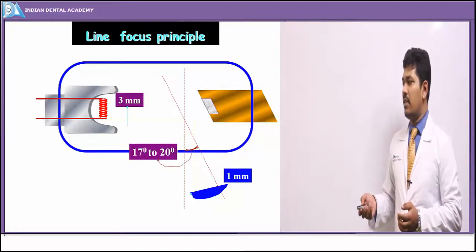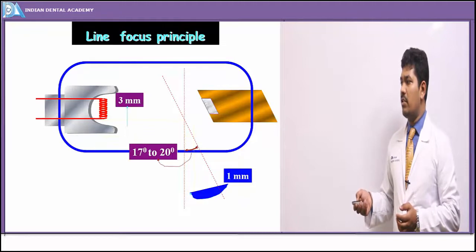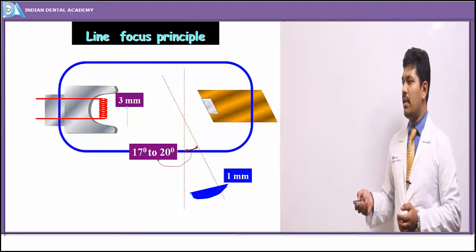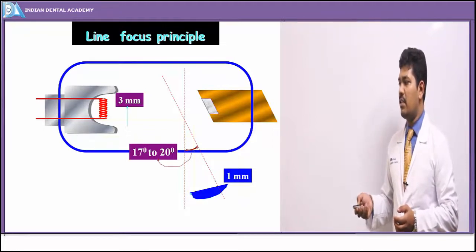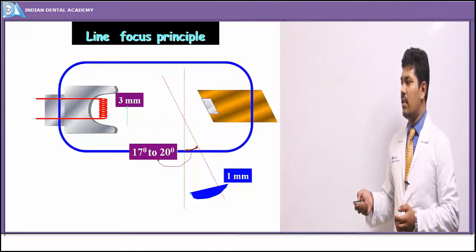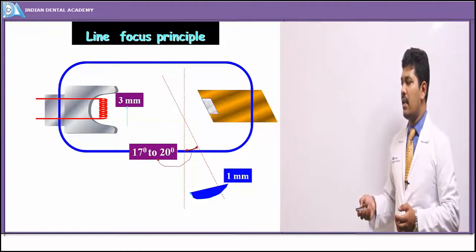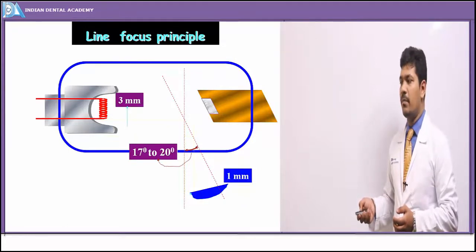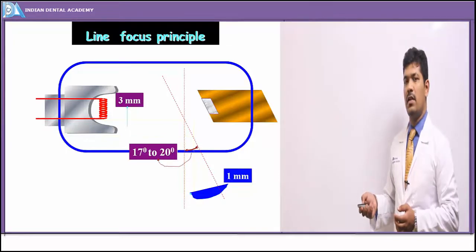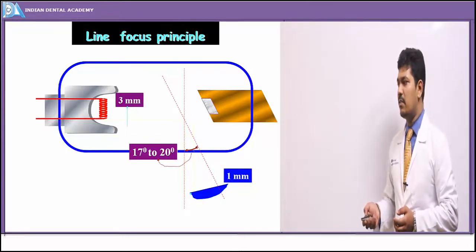As shown in the diagram, the actual focal spot is around 3 mm in dimensions, and because of the angulation of 17 to 20 degrees, the effective focal spot is just about 1 mm — taking into consideration both heat loss and sharper image detail.